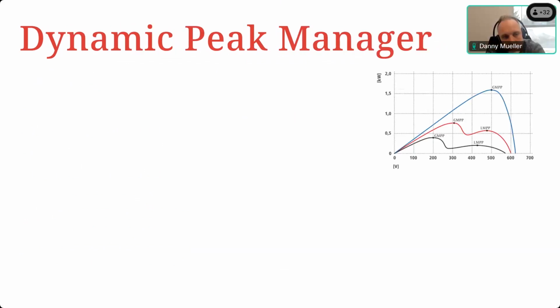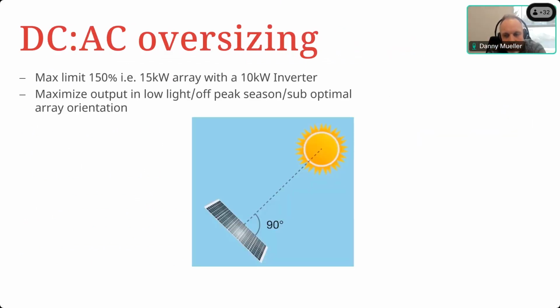We've seen the same, and it's become a real problem because it doesn't have the latest certification, and a lot of places where these units are sold require the SB certification that Fronius currently doesn't have with the old Primos. Now, although we are not 1741 SB certified, despite not having the certification, the inverter actually meets a lot of those requirements. So if there are special situations where they're more keen on the ride-through capabilities and things like that, the inverter meets all of those without the certification itself.